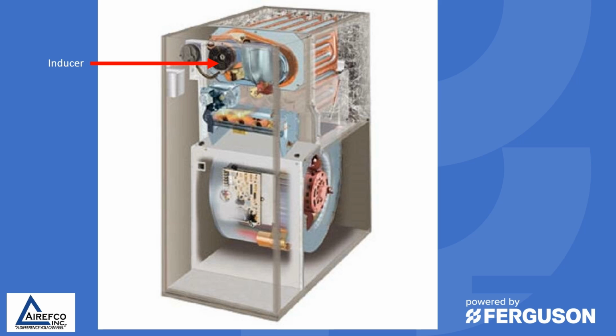furnace to operate correctly. Make sure that the blower wheel of the inducer motor is clean, and make sure that the inducer is coming up to correct speed. This can be done by observing the pressure switches, which have a certain number of water column inches that need to be made before the contacts in the pressure switch will make. If they are making, this means the inducer motor is coming up to proper speed. Make sure the pressure switches operate correctly, as they are safeties for the correct operation of the furnace.